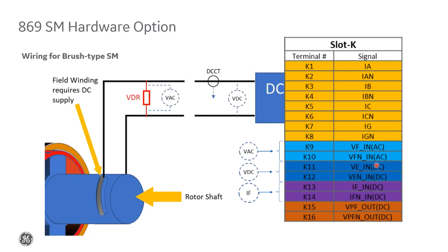And just to reiterate, here's a closer look of the terminals. This is the synchronous motor option terminal block here. The first two inputs, again, for the field winding voltage, which is measured across the discharge resistor. The second set for the exciter voltage, and the set highlighted purple to take the DC-CT field current measurement. So this would be a fully wired application for a brush type motor.